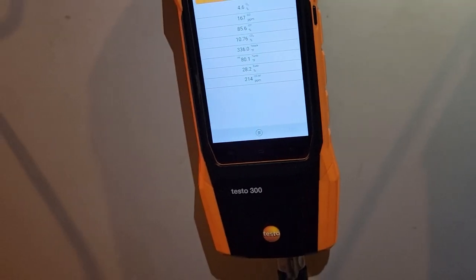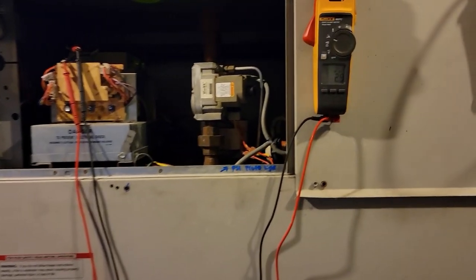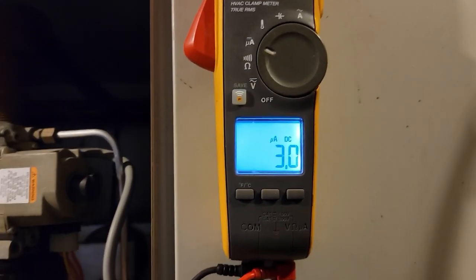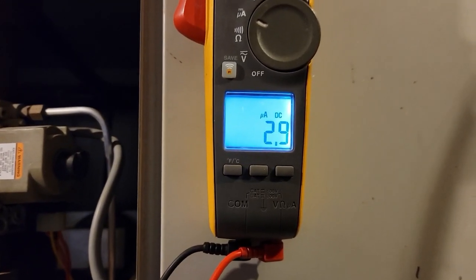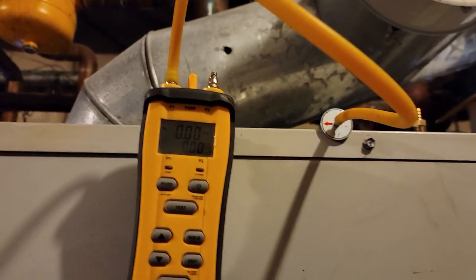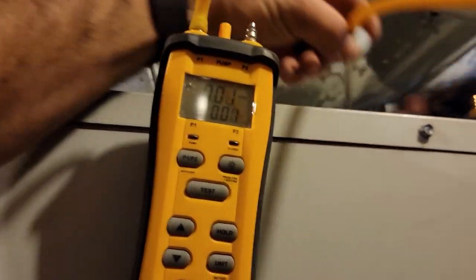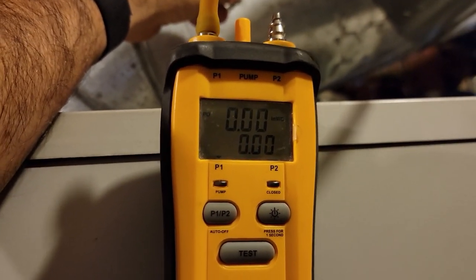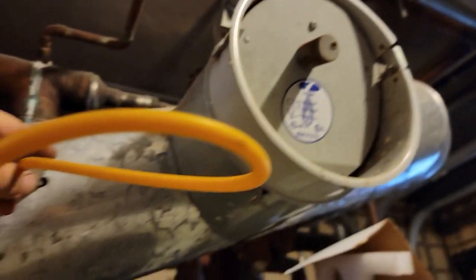We're back again because of flame failure. It drops out at two microamps. Started out at 2.3, 2.4. Check my draft. We're right in there. This ain't the right probe, but better than nothing. We are not overly drafting, and we are teeter-tottering. Supposed to be like 0.001 negative.